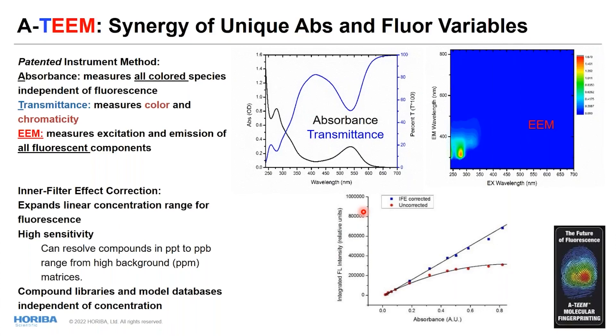A key patented feature is correction of inner filter effects. Previously, fluorescence analytical spectroscopy was held back because the light transferring through the absorption path and leaving the measurement cell is absorbed before reaching the detector. We correct for this on the fly as we acquire data simultaneously. This allows higher sensitivity, broader concentration ranges, and — critically — spectra representing pure chemical species that can be stored in libraries and databases.